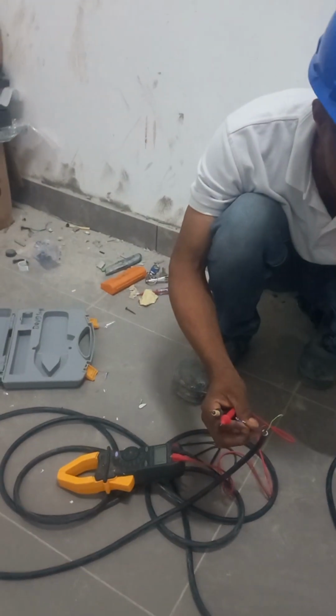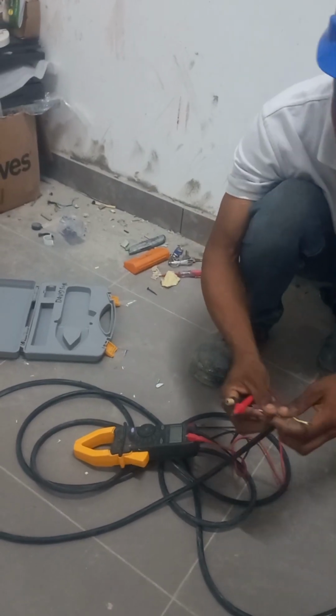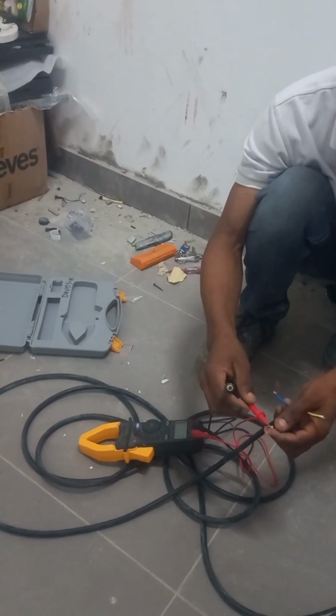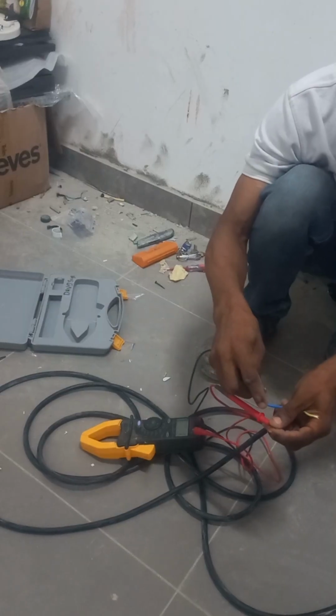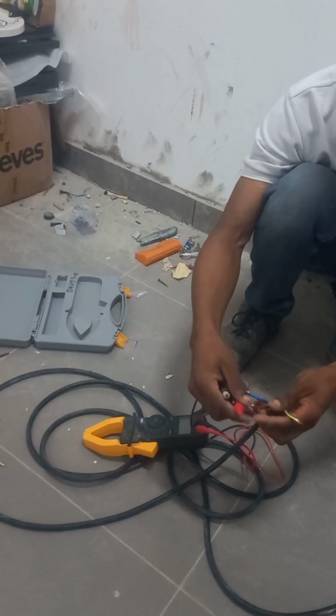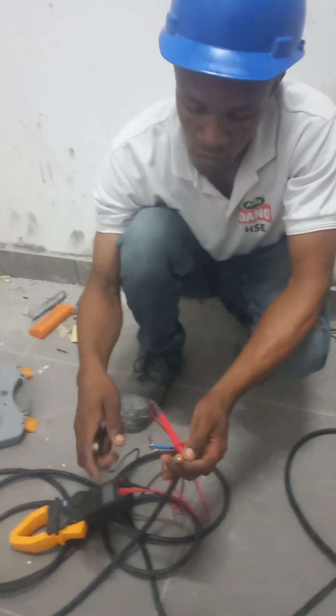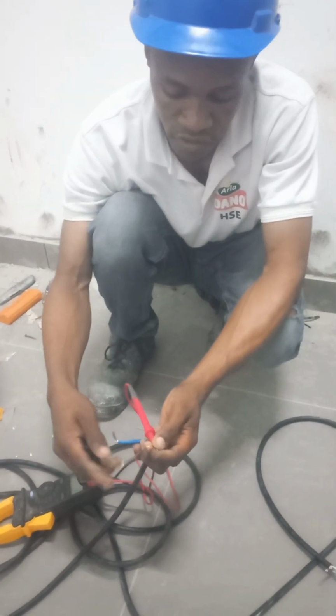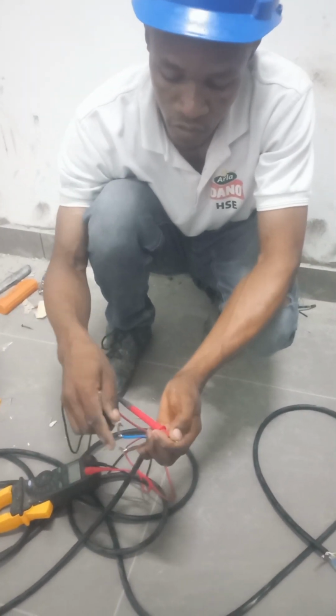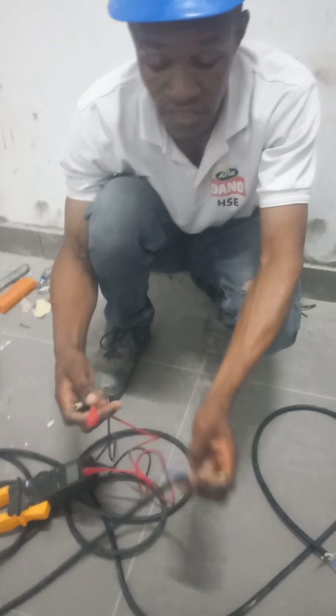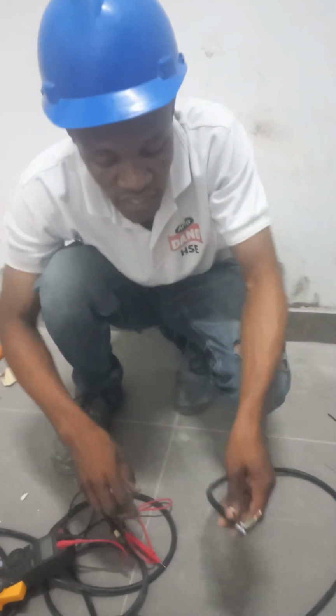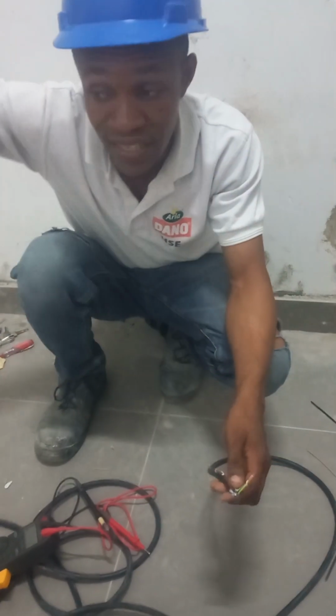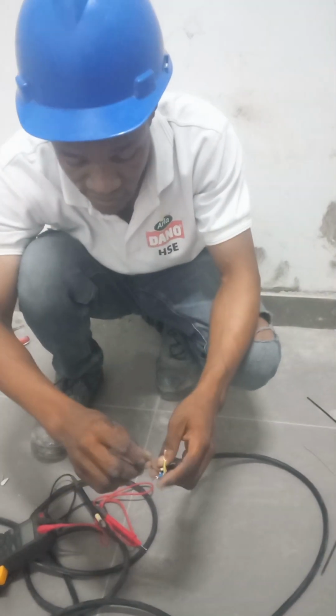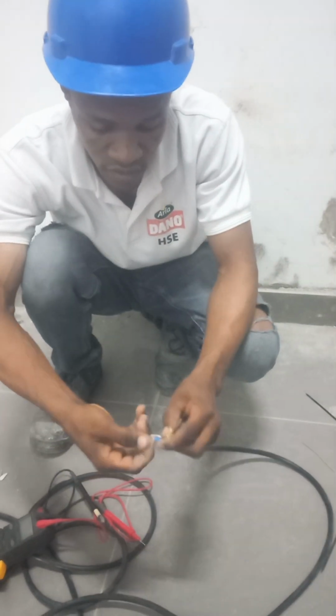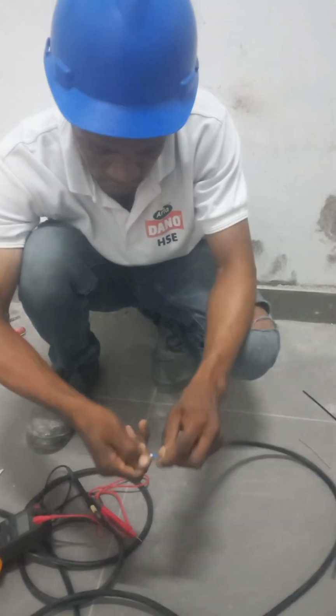So if you want to check the continuity of this cable, without closing this end, you first of all check. This is brown, this is blue. It's not making noise. You check brown to earth. It's not making noise. You check earth to blue. It's not making noise. So you can see now it's not connected. Now if you want to check if this cable is true, it can be 1000 meters, it can be 2000 meters, it can be 5000 meters, you join this brown and blue together.